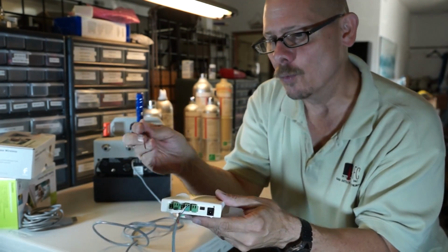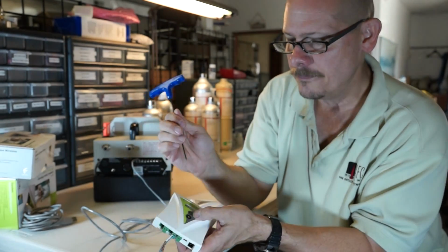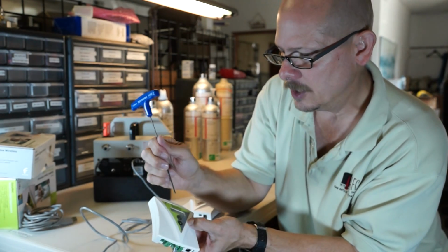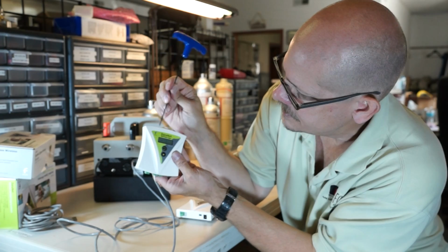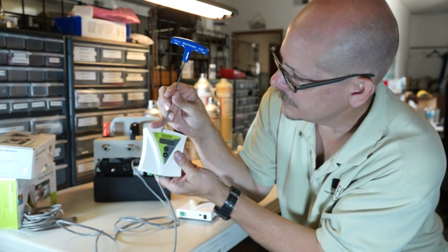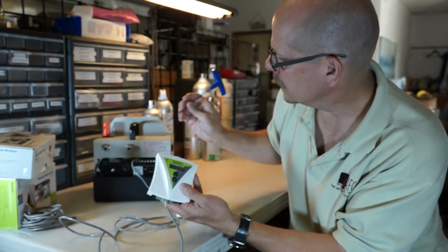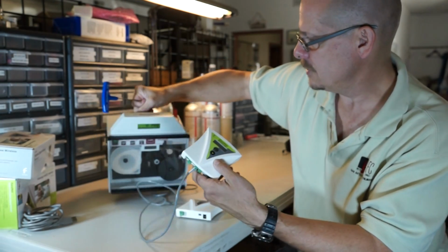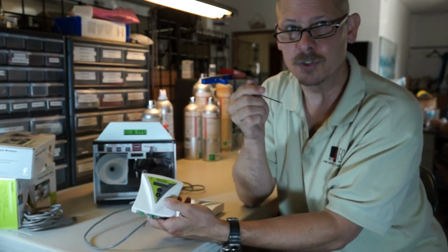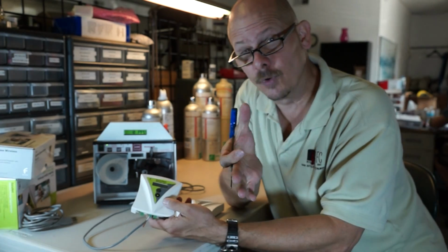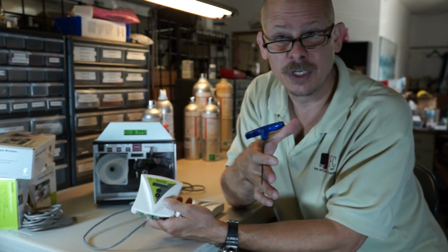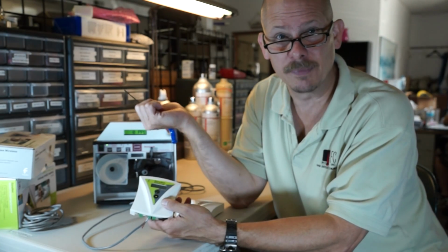And now we're taking that signal, and I can hit this button and it'll tell me, yep, certainly I am getting an input from this device, and it's telling me we're at 4 milliamps. Why is that? Because our instrument is reading 0. So 0 is always 4 milliamps. And 20 milliamps is going to be the highest range, or the maximum range of the device you're monitoring.